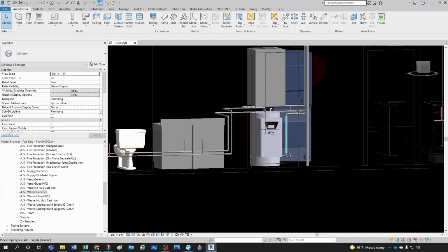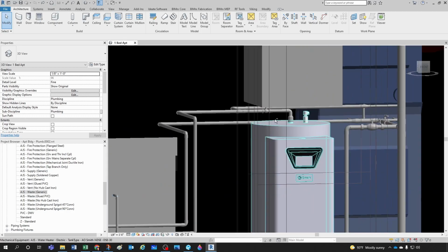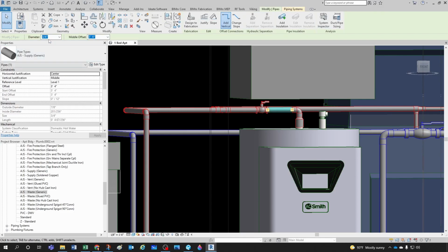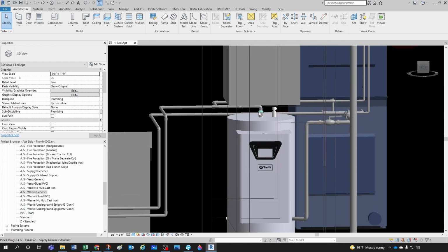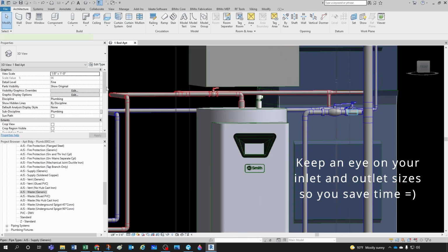And one thing I missed here is that if our hot water demand to the hot water fixtures is such that our pipe exit in the water heater is 3/4 of an inch, then the inlet pipe to the water heater should also be 3/4 of an inch. And I don't think that's what we had. Let me see. Yeah, so we had 1 inch.